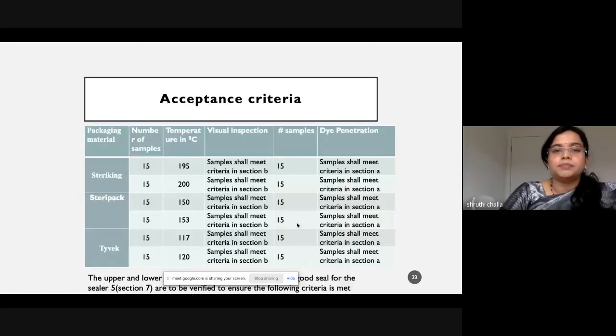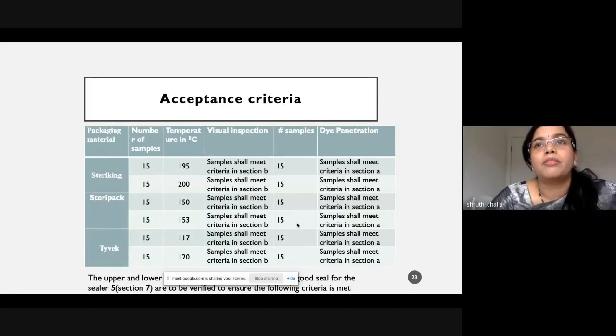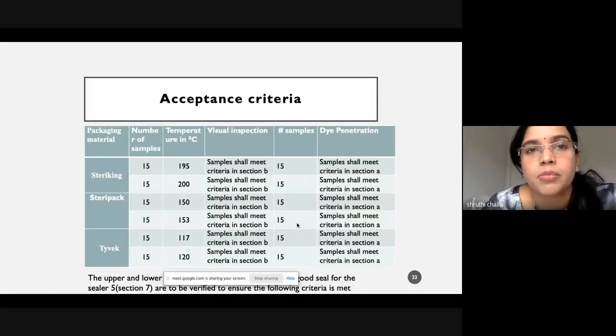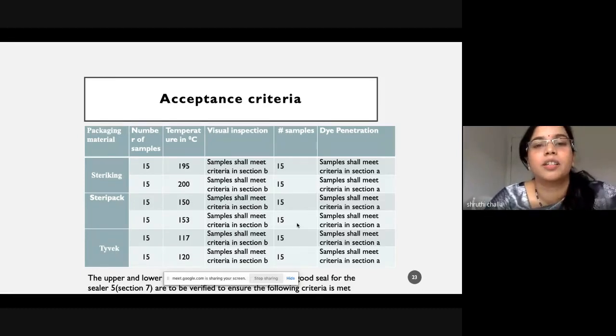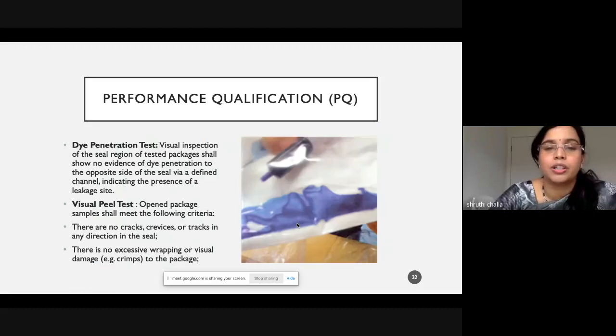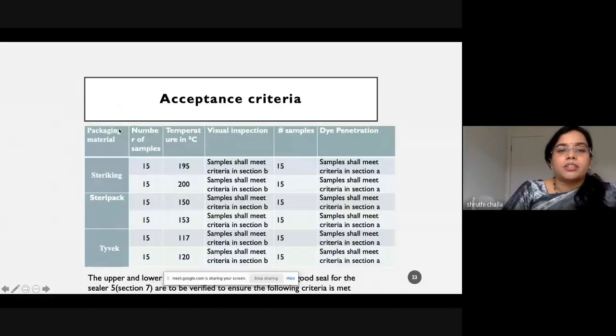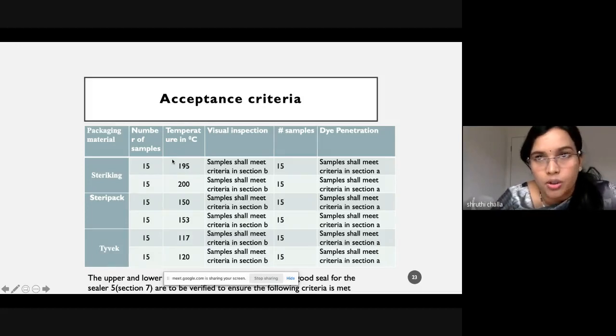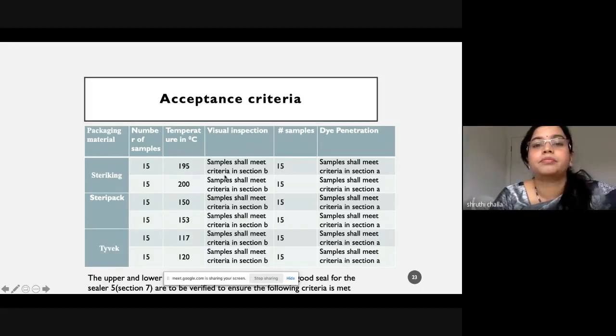So this is the record. In the previous example of process validation, I included the protocol, and this time I have included the record. So this is the sample record. We have taken the samples. The number of samples would be 15 samples. The temperature, we are checking at 2 different points, 195 degrees and also 200 degrees. We have taken these two as the operating range of the sealer. And we do check for visual inspection as well as dye penetration.